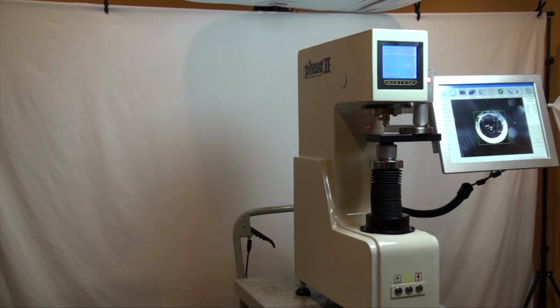This is an instructional video detailing the applications and functions of the Phase 2 Z-axis Brinell Hardness Tester. These hardness testers are designed to test primarily metals using the Brinell Hardness Method via a closed-loop, load-cell-driven control. This replaces the older weight-loaded systems where the testing performance was not as consistent or as accurate as the current load-cell system. Now let's move over to the operation of the hardness tester and see how easy it is to utilize the different functions, taking tests, and obtaining results.